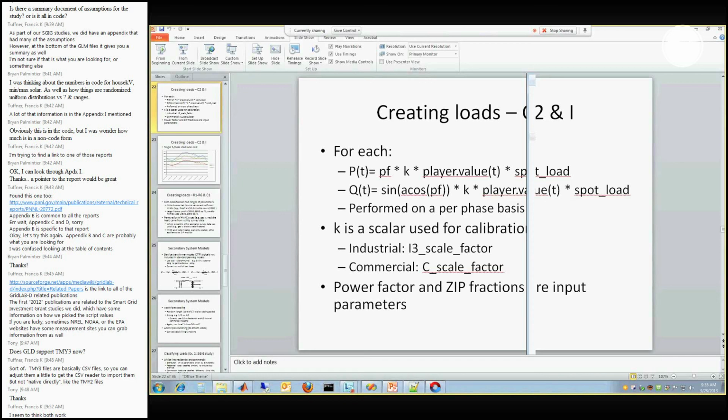Yeah, because we were having trouble interpreting some outputs we were getting, and we got different direction currents on phase A versus B and C, and I wanted to make sure that there was nothing else we were doing driving it directly to cause those. So now we can debug why the current direction of some nodes is weird.